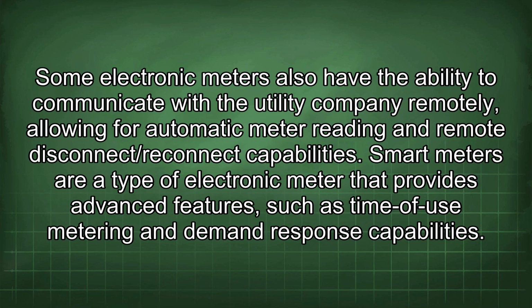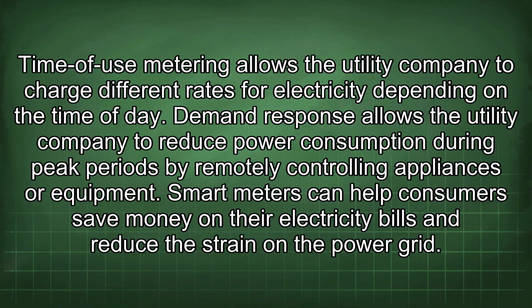Some electronic meters also have the ability to communicate with the utility company remotely, allowing for automatic meter reading and remote disconnect/reconnect capabilities. Smart meters are a type of electronic meter that provides advanced features, such as time-of-use metering and demand response capabilities. Time-of-use metering allows the utility company to charge different rates for electricity depending on the time of day. Demand response allows the utility company to reduce power consumption during peak periods by remotely controlling appliances or equipment. Smart meters can help consumers save money on their electricity bills and reduce the strain on the power grid.